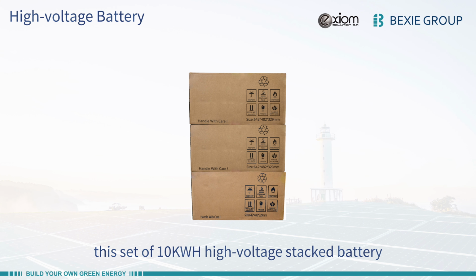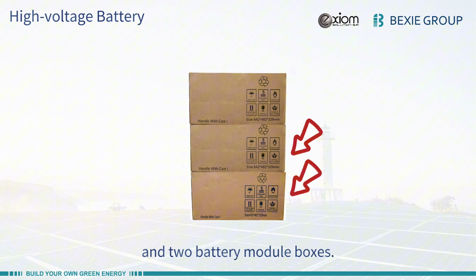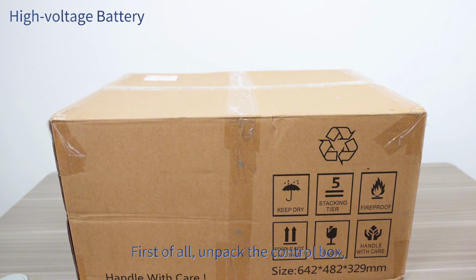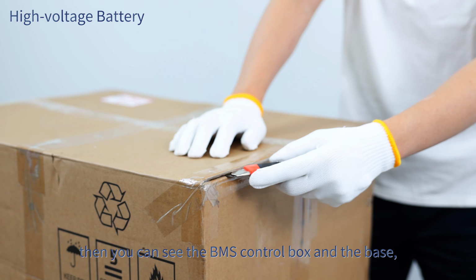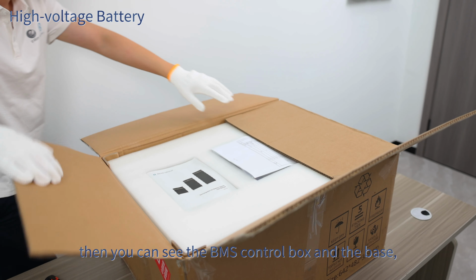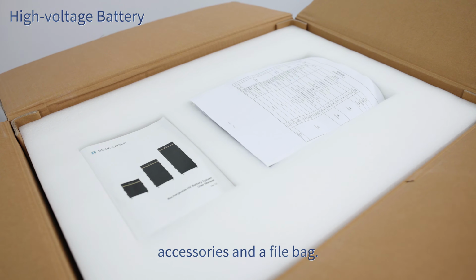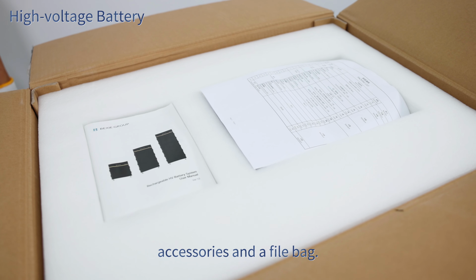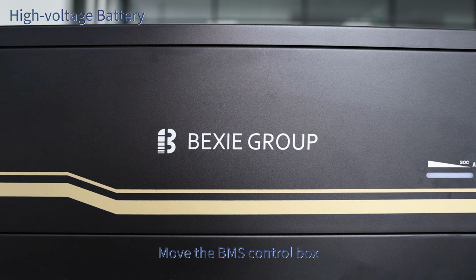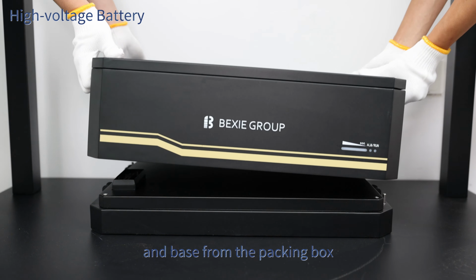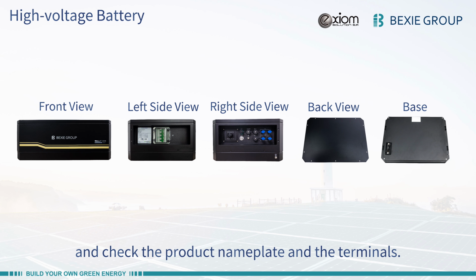This set of 10 kilowatt hours high voltage stacked battery contains one control box and two battery module boxes. First of all, unpack the control box. Then you can see the BMS control box and the base, mounting brackets, accessories, and a file bag. Product display. Move the BMS control box and base from the packing box and check the product nameplate and the terminals.